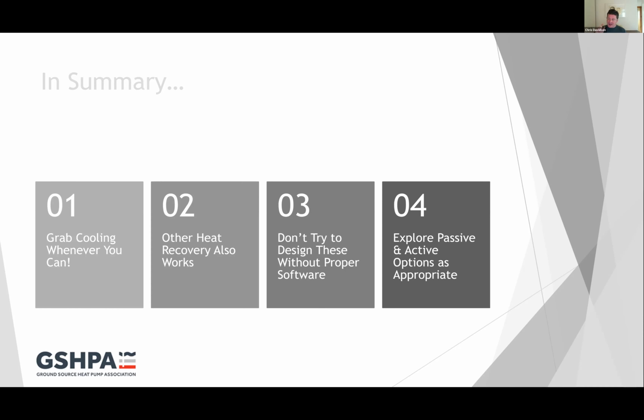When you get into a more balanced heating and cooling system, you can start to compress those spacings down. You don't just avoid losing out, you can actually win a bit, because you're packing your boreholes together and creating a more effective thermal store. It's something we can do in our design software, and other design software out there can do it too, you can start messing around with spacings to see where the optimum is, and see if it's starting to be heating driven or if cooling and heating is balancing in the system. With experience, it's a really interesting thing to mess around with.